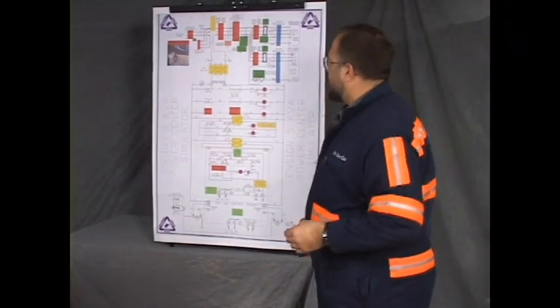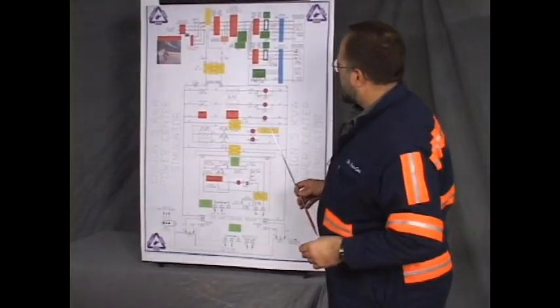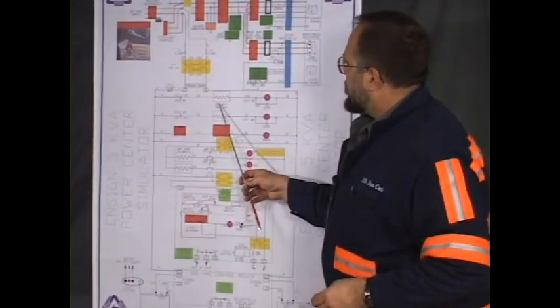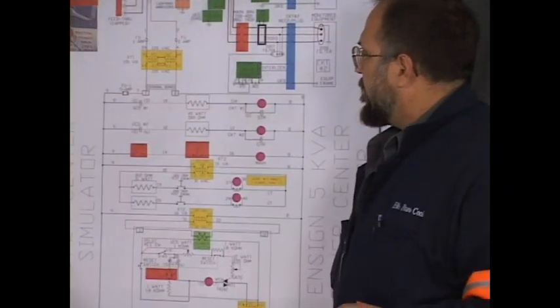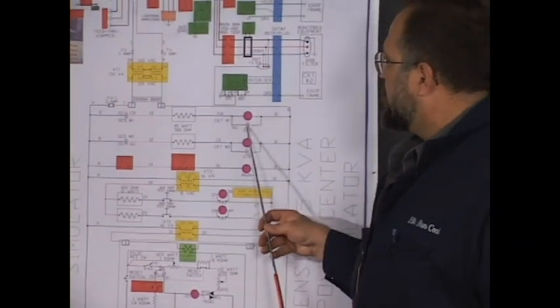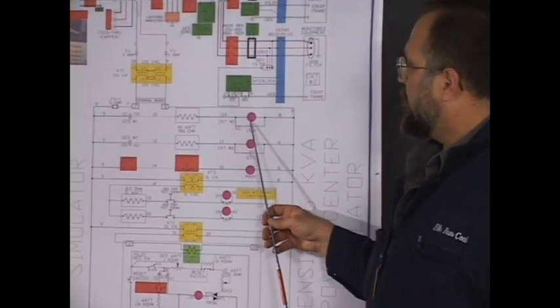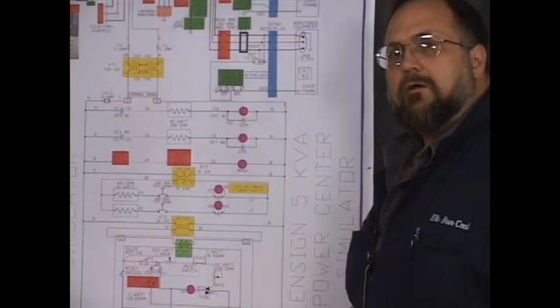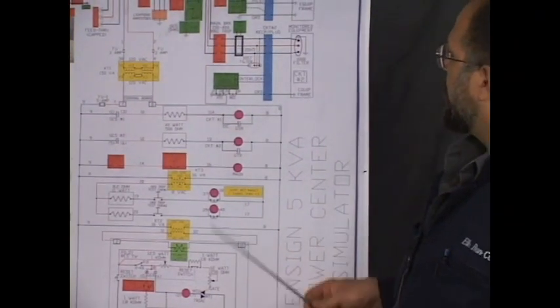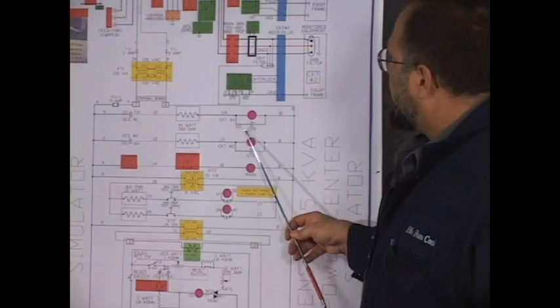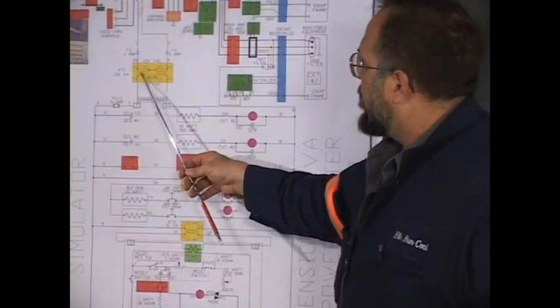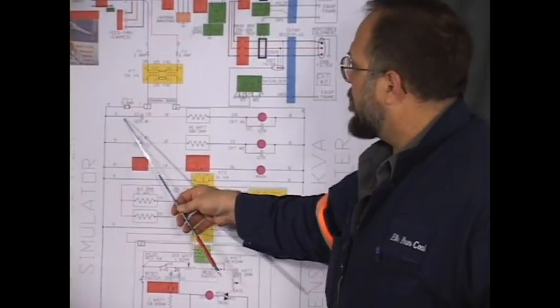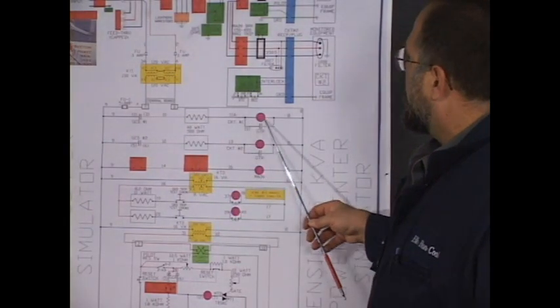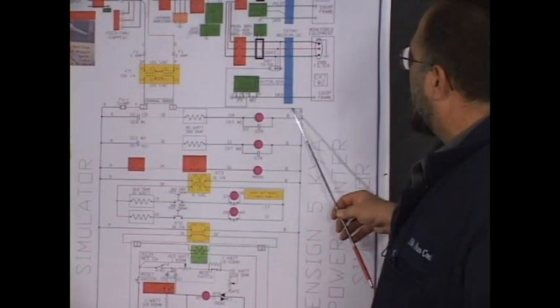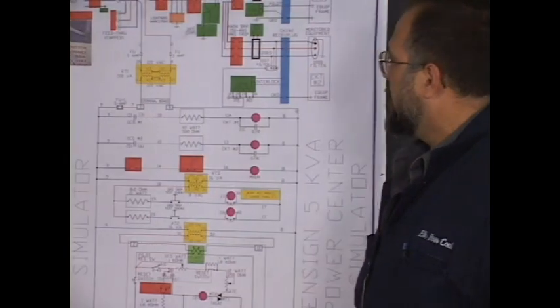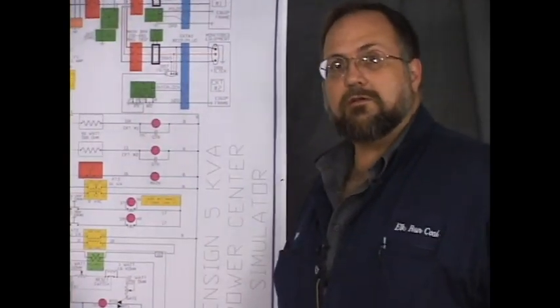It's exactly the same thing. At that time, I told you that the reason this 40 watt 500 ohm resistor is in place is so that when we close the GTR contacts to rob the UVR of control power for a ground fault trip, that would make a short circuit. It would connect X4 of KT1 straight through to wire number 8 back to X1 with no load. That would be a short circuit.